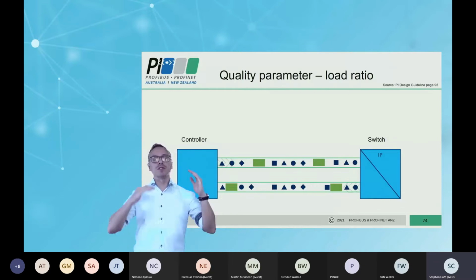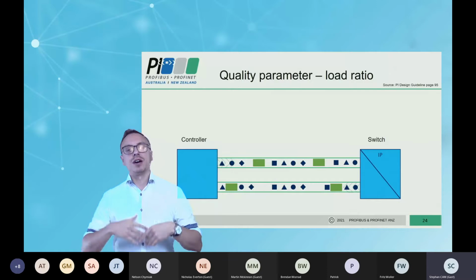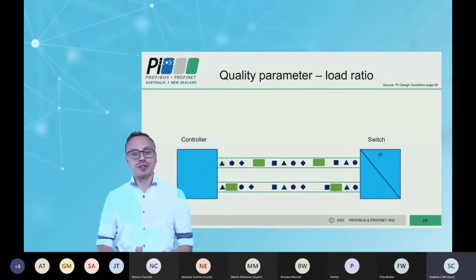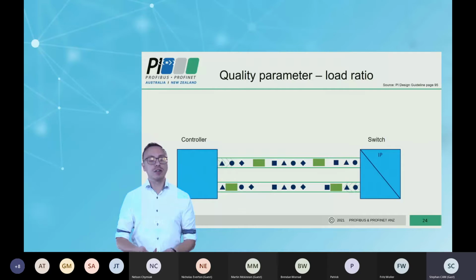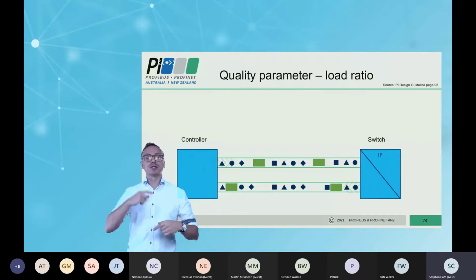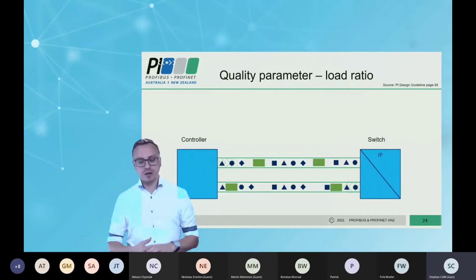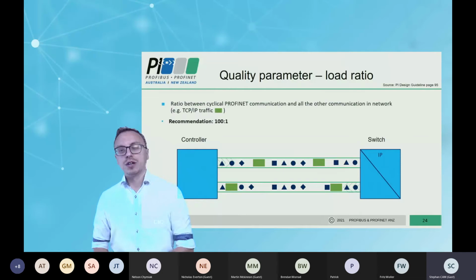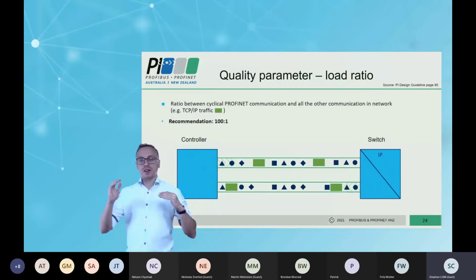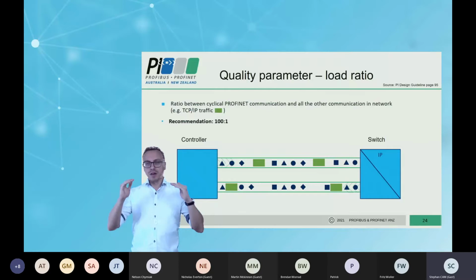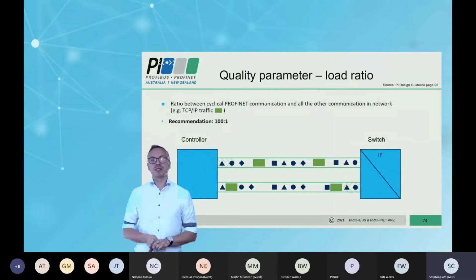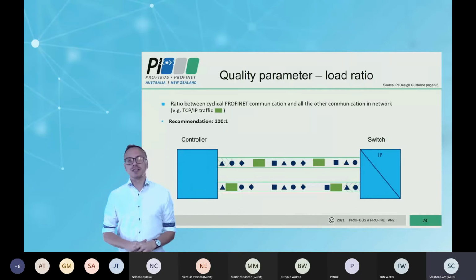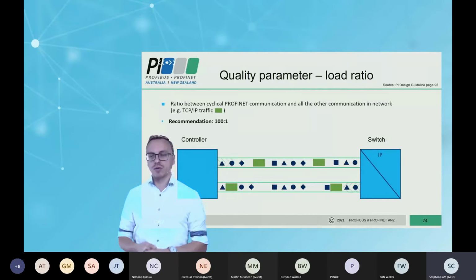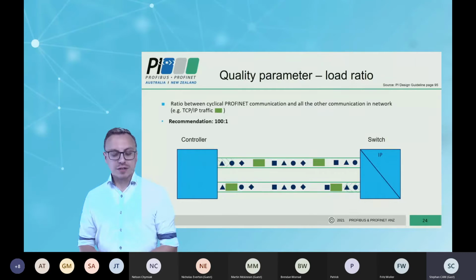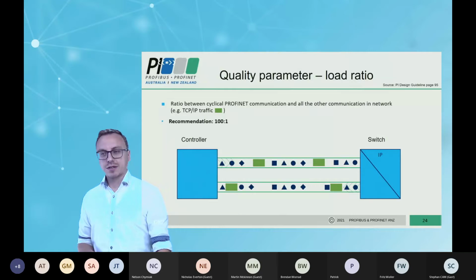Because if you have a lot of Ethernet frames in your system, as I said, it could create jitter or it could create net load. And this will disturb your cyclical communication, your PROFINET network. This is why it's important to look at the ratio between these two kinds of frames. And here the recommendation is 100 to 1. So that means 100 PROFINET frames and 1 Ethernet frame in this measuring time.